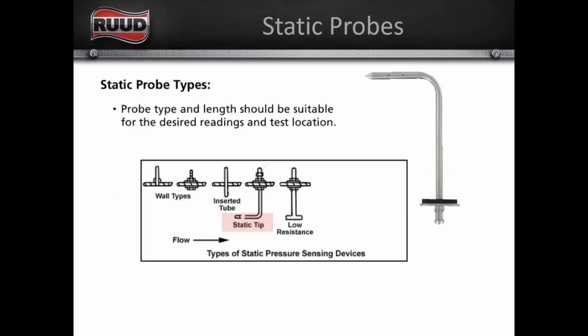So you also want to, and a lot of measurement devices, a lot of manometers or magnehelic gauges, don't necessarily come with static probes. It's usually best if you have them. I recommend them. I have a pair. You don't have to have pairs. You can measure your return and your supply and just add those whole numbers together. But I don't know how clear it shows on what you can see, this static pressure probe is a piece of tubing with a 90-degree bend in it. And the very end of that is capped off. And you can see on this one, on the side that we're looking at, there are two small holes drilled in the side of this static pressure probe.